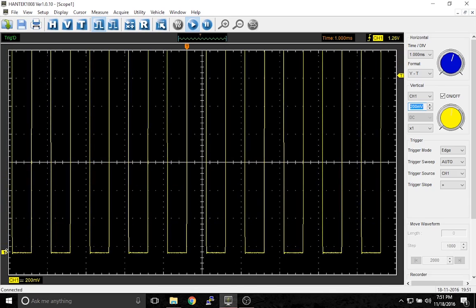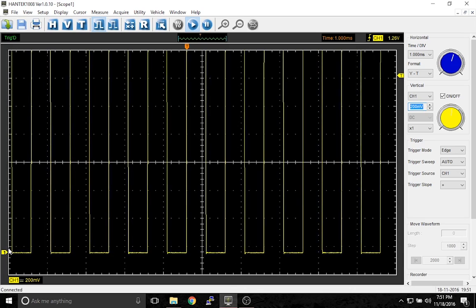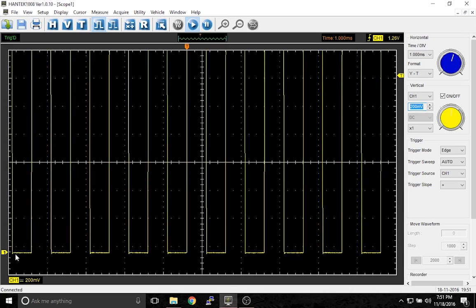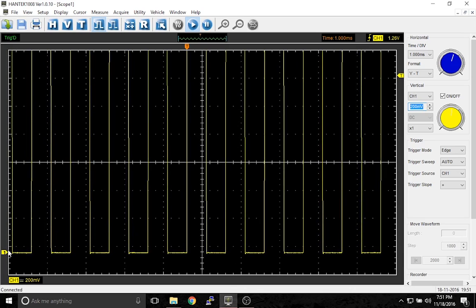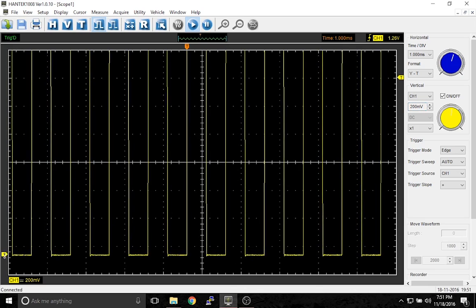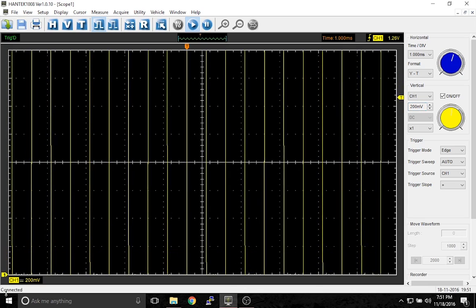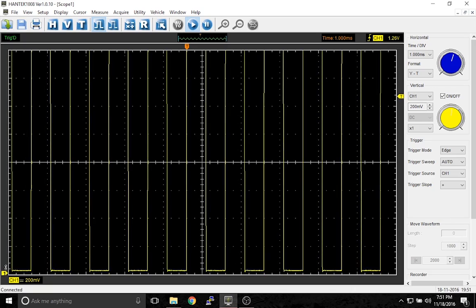The way we could fix that, well not completely fix it but make it look a little better, is by moving the zero point. This one here tells the scope where zero volts is for this channel.